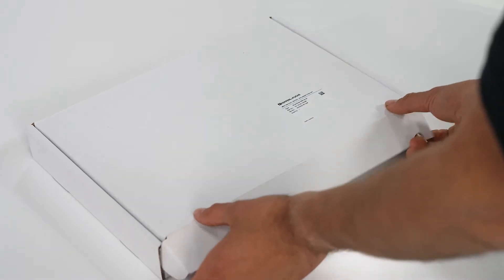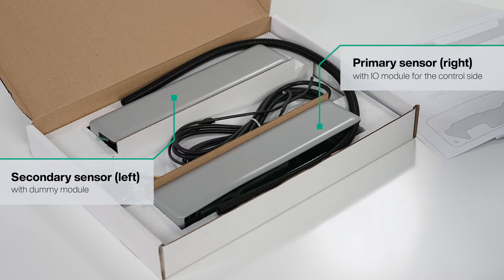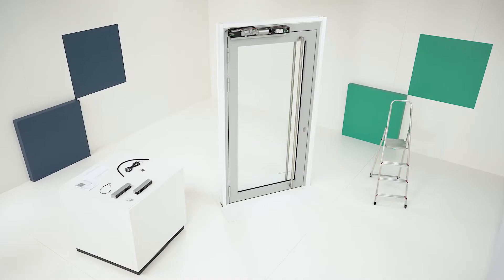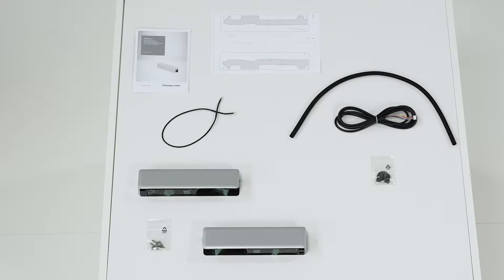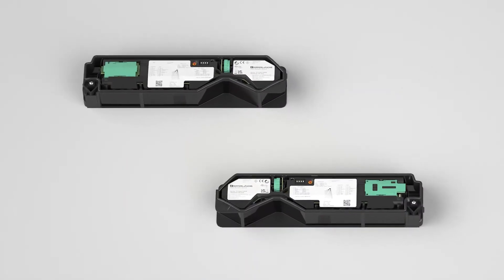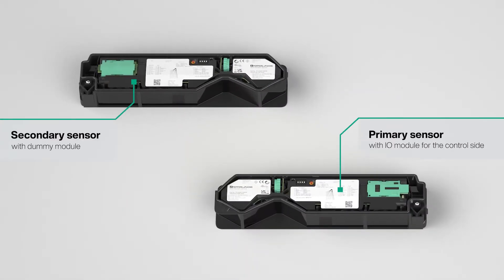All of the components required for installing and commissioning the shield scan are included in the scope of delivery. On delivery, the I.O. module is connected to the right-hand sensor. The primary and secondary sensors are assigned by connecting the I.O. module to the sensor that will act as the primary sensor. The conditions at the installation site determine which sensor should be assigned the primary role. Ideally, the I.O. module should be installed on the control side.